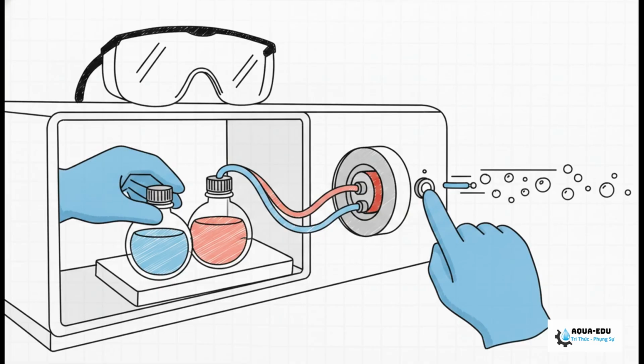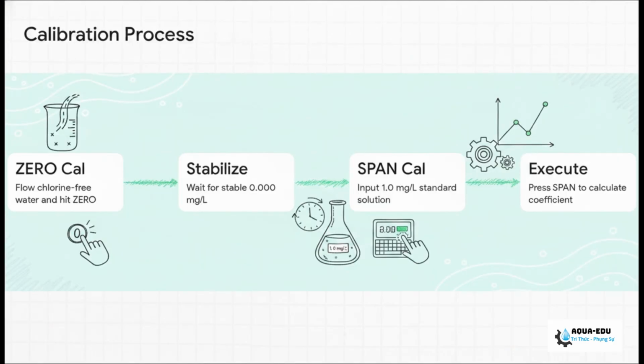Once everything is securely connected, press the prime button to fire up the peristaltic pump. You must purge every single air bubble out of those chemical lines. Seriously, not a single bubble can remain. Let's move on and actually build our calibration curve.